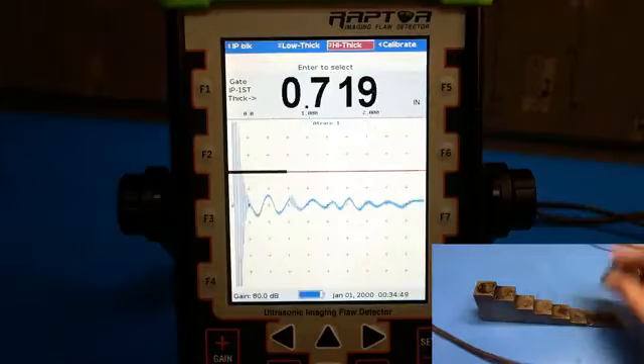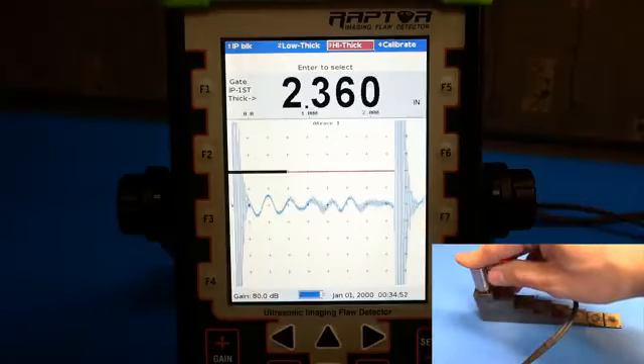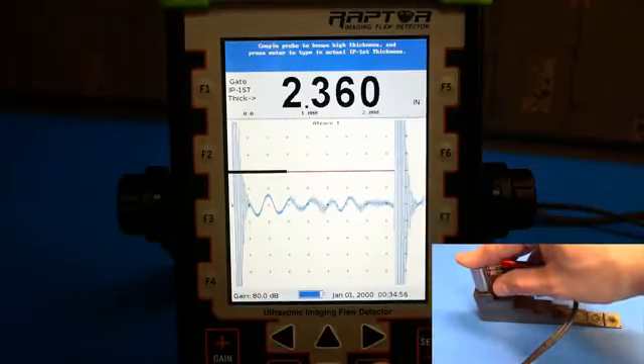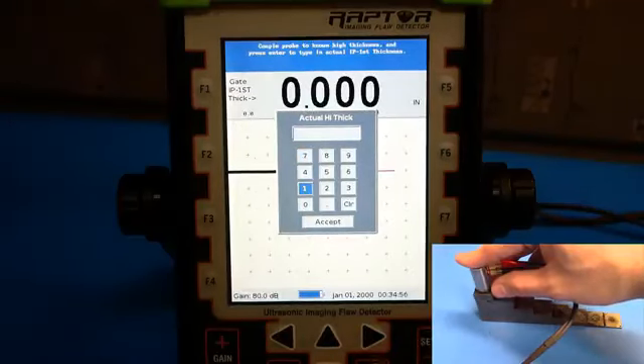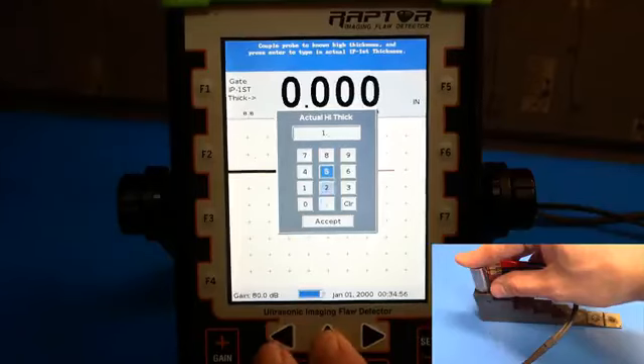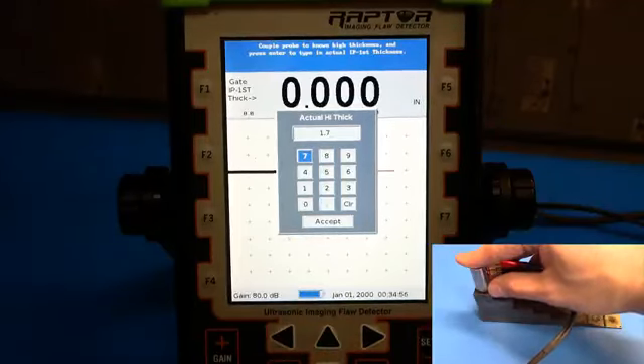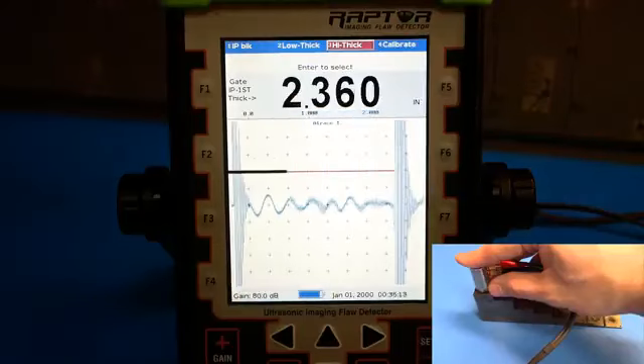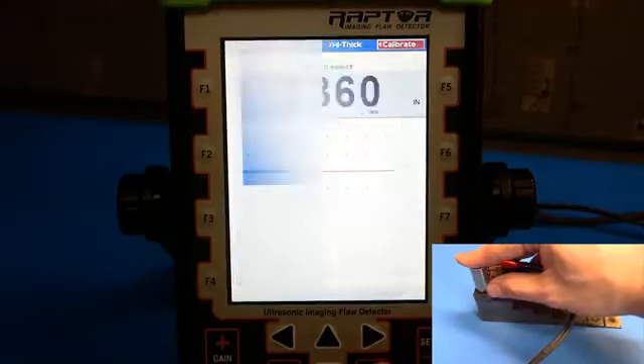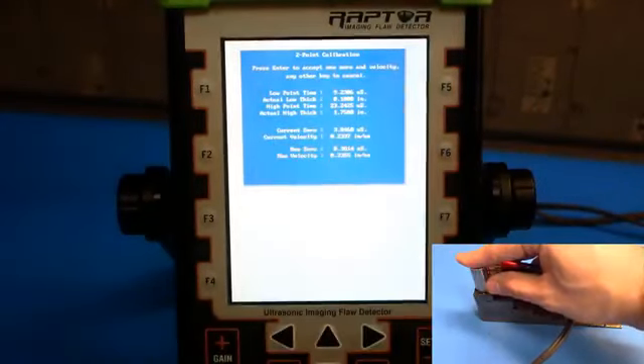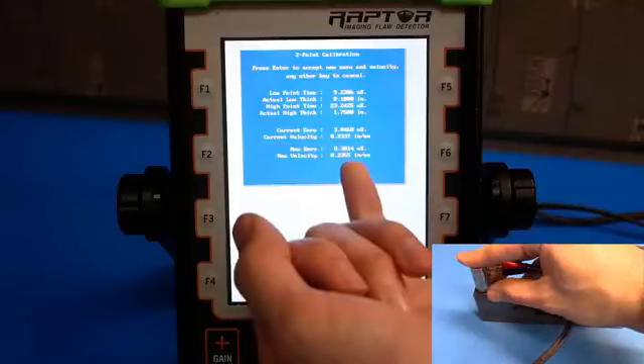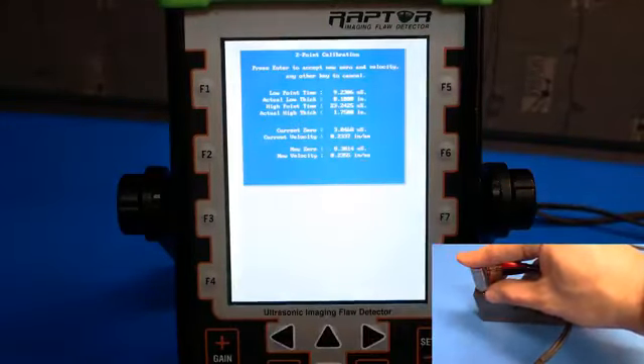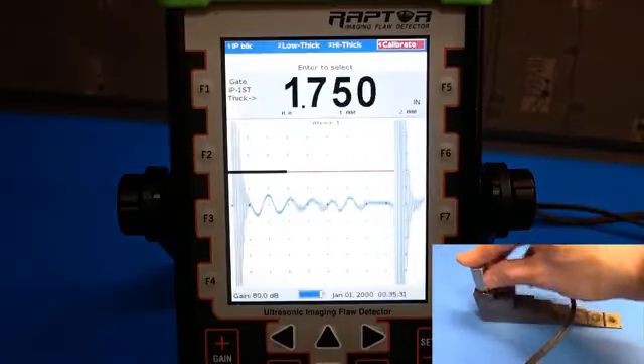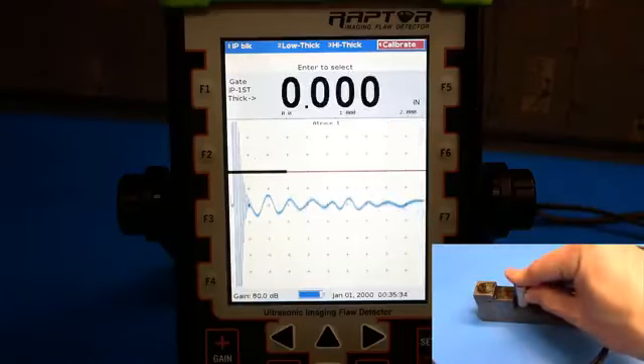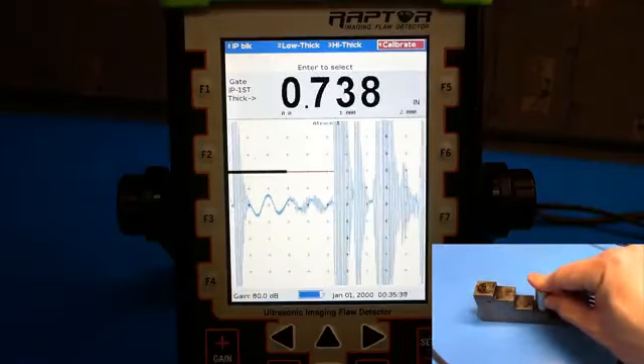Next, navigate to high thickness and couple to the high thickness on your step block. Push enter, enter again, and enter 1.75 inches. Again, these are the values for my step block. If your step block has different values, use those values. After you've done that, hit calibrate, and the gauge will give us a list of adjustments that it's made, our new zero point, and our new velocity of sound. Push enter to accept. You can go through the step block to verify that the calibration is satisfactory.